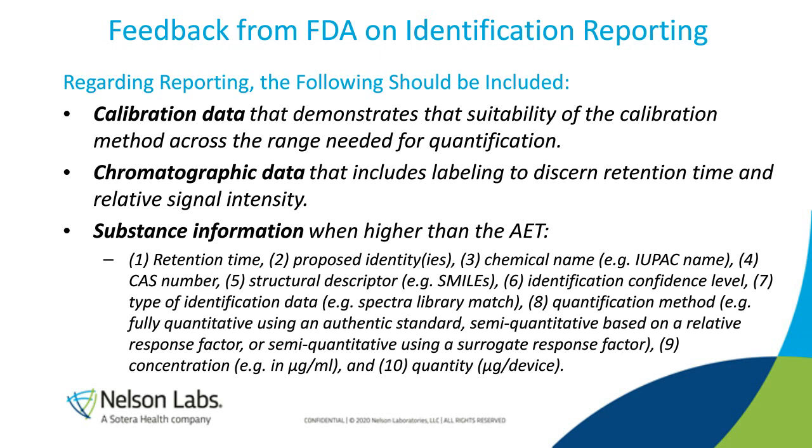They want to see retention time, proposed identities, the chemical name, the CAS number, and I would say here it should say CAS numbers, because it is true that lots of compounds have more than one CAS number. Structural descriptors, like a SMILES structure or an actual picture of the structure itself, the identification level, type of identification data used, quantification method, concentration finally, and then the quantity in micrograms per device.